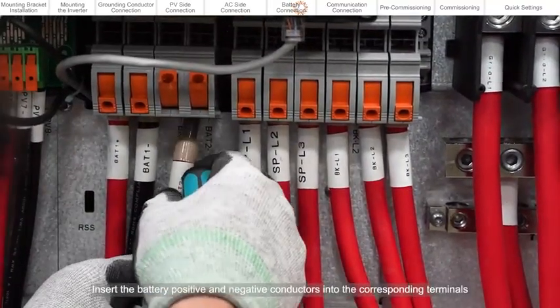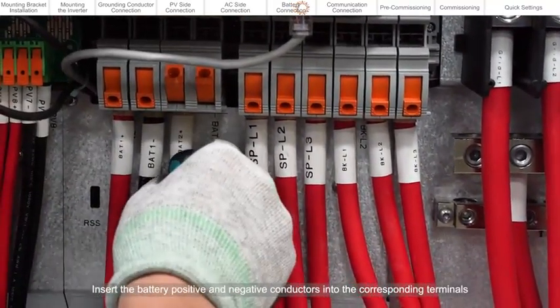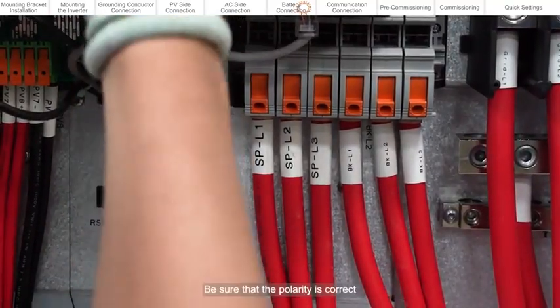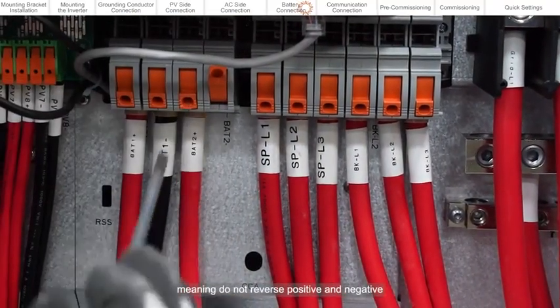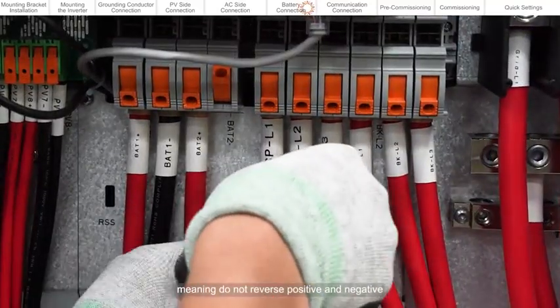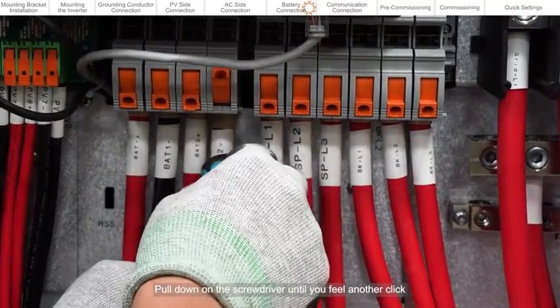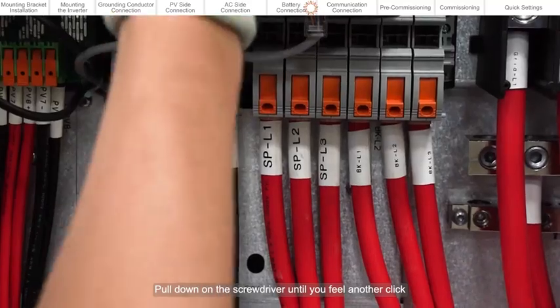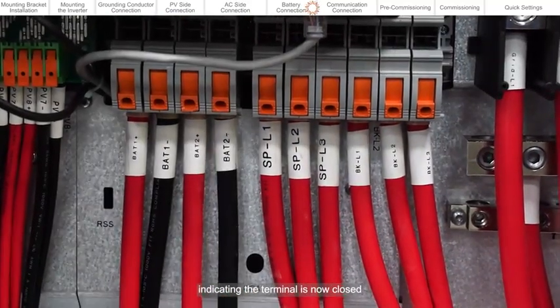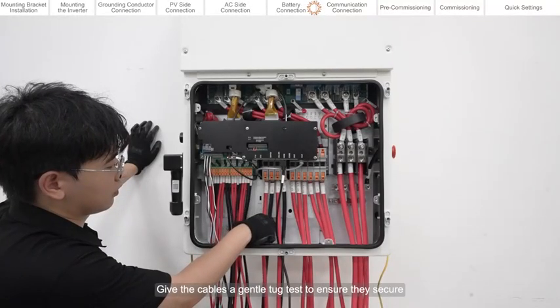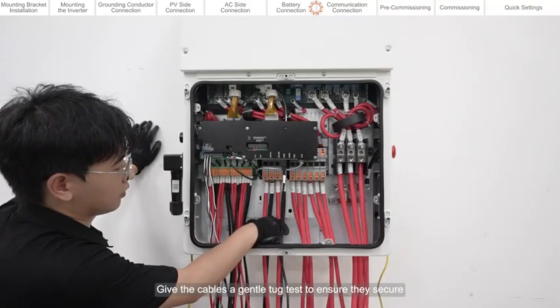Insert the battery positive and negative conductors into the corresponding terminals. Be sure that the polarity is correct, meaning do not reverse positive and negative. Pull down on the screwdriver until you feel another click, indicating the terminal is now closed. Give the cables a gentle tug test to ensure they are secure.